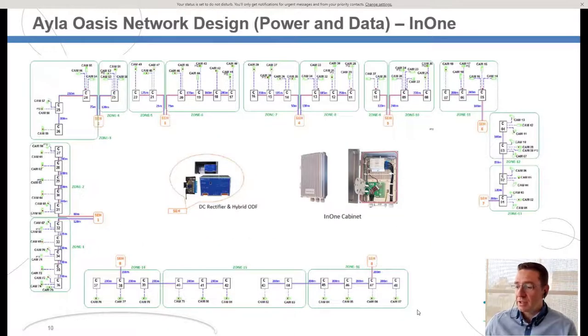This is the design, which Jawad mentioned briefly. These orange boxes are the locations where AC power was provided and we put rectifiers. We spread the project into 16 zones with 9 AC power sources for the whole project, while in the traditional design they needed 57 locations, because they had 57 cabinets, 57 locations to provide AC power — it was a really big project for them.